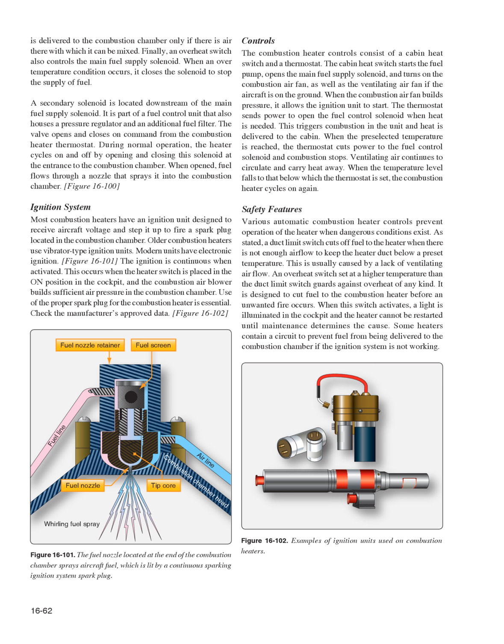When the preselected temperature is reached, the thermostat cuts power to the fuel control solenoid and combustion stops. Ventilating air continues to circulate and carry heat away. When the temperature level falls to that below which the thermostat is set, the combustion heater cycles on again. Safety features: various automatic combustion heater controls prevent operation of the heater when dangerous conditions exist. As stated, a duct limit switch cuts off fuel to the heater when there is not enough airflow to keep the heater duct below a preset temperature. This is usually caused by a lack of ventilating airflow.